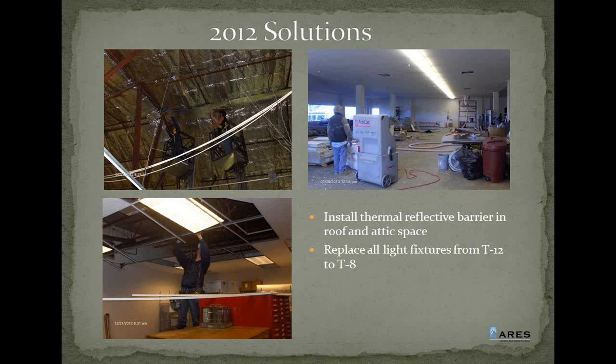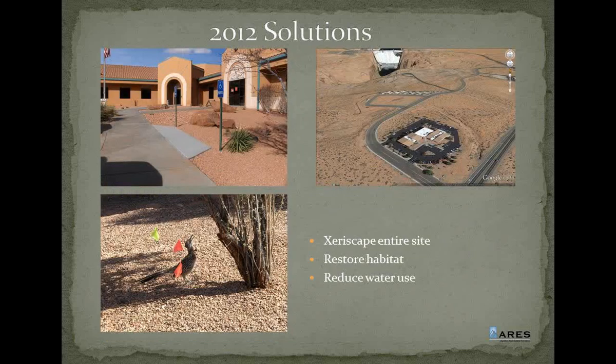For those of you that don't know what that means, your optimal RTU operating temperature in a plenum space is 85 degrees or less. So imagine you're cooling this air down 55 degrees, you're running it through an uninsulated plenum space that's 115. By the time it gets delivered, it's already at 75 degrees. So there's a huge issue there. We changed out all of the T12 light fixtures to T8s. We got rid of all the magnetic ballasts and exchanged those for electronic ballasts. And then we insulated all the spaces that didn't have insulation, and we looked in every single wall, every floor, every ceiling, and found space after space after space where the insulation hadn't been put in the original construction.